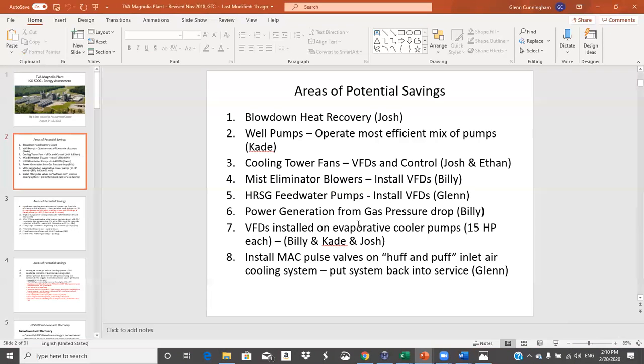We were thinking about the big feed water pumps. Those things are probably 2,000 horsepower, something like that. And if you look at where the feed water actually enters, they just have a throttling valve, a control valve, and it opens and shuts. Again, it's not very efficient, but it was just too expensive. They're also medium voltage, those things were probably 4,000 volts, and as you go up in voltage, these drives get much more expensive. So that did not make the cut. These were ideas that were generated, and then some of it actually got written up, and some of it didn't.